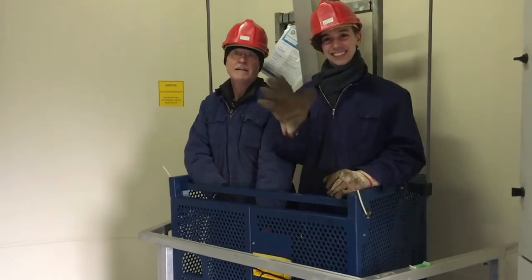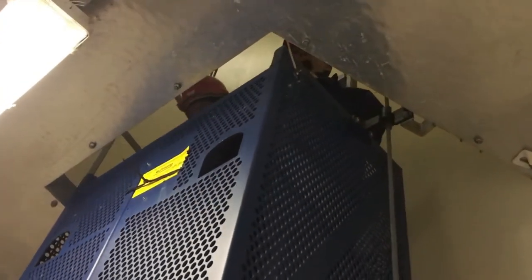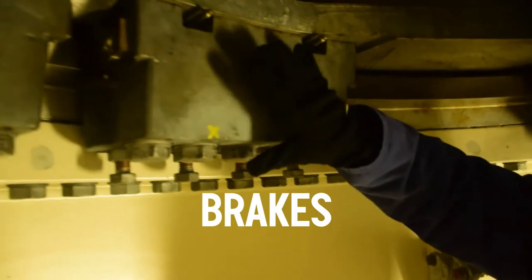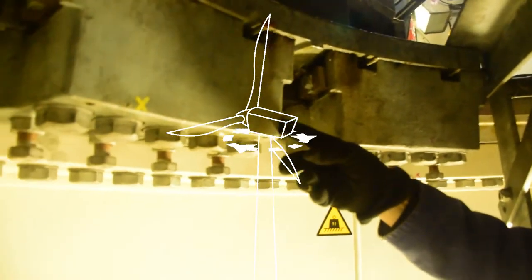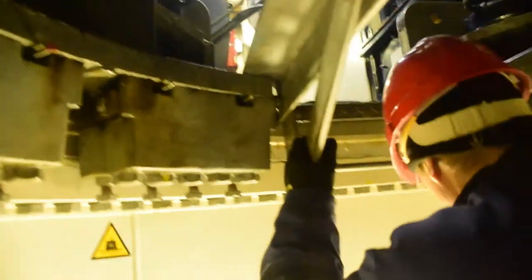Woohoo! You must pay attention. So here we are in the top of the turbine. We just went up a really scary escalator. So where are we now? We are under the so-called Azimut system. Here we have the Azimut brakes. When you look there, we have the motors which turns the nacelle on the tower. So that stops that from twisting — because you wouldn't want this cable to twist and break. Yes, if it turns three times, the system stops and turns lower. So it's just starting moving — this is all being done automatically. So it's just a little adjustment. That was very cool.